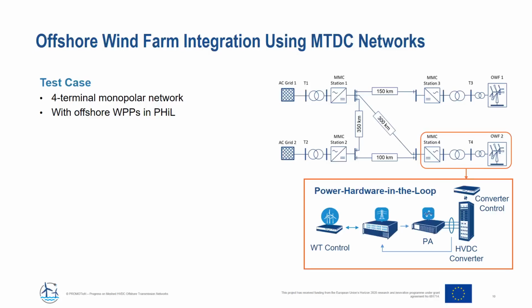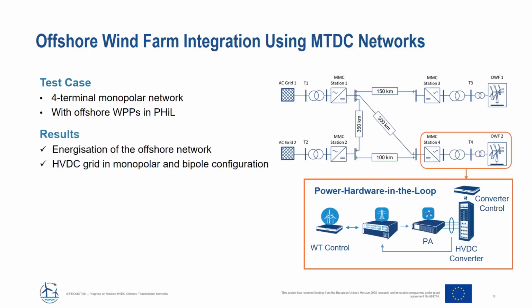So in the end, the MMC converters, the HVDC converters, are physical devices which are directly connected to a 4-quadrant power amplifier. And this power amplifier is controlled by using a real-time simulation of the collector grid, which is connected to a wind power plant controller or wind turbine controller. Overall, using this setup, we have been able to show that the energization of the offshore network can work properly, and that the HVDC grid can be controlled in monopolar and bipolar configuration.